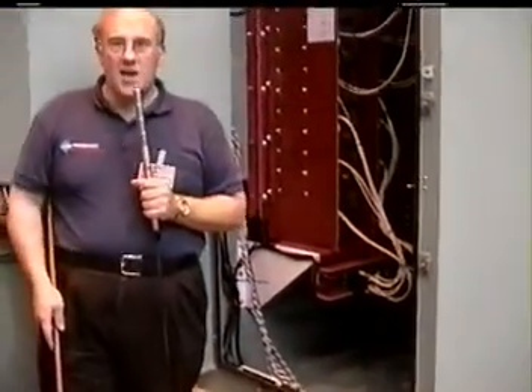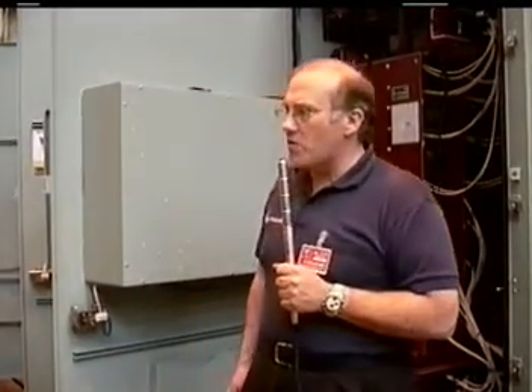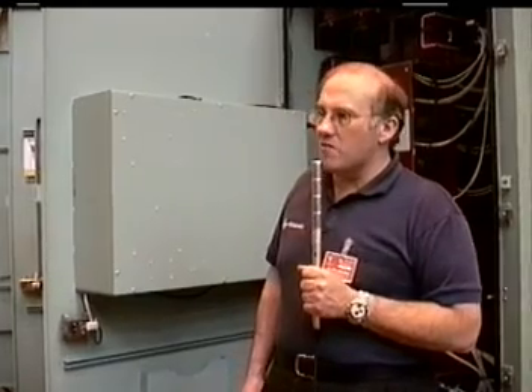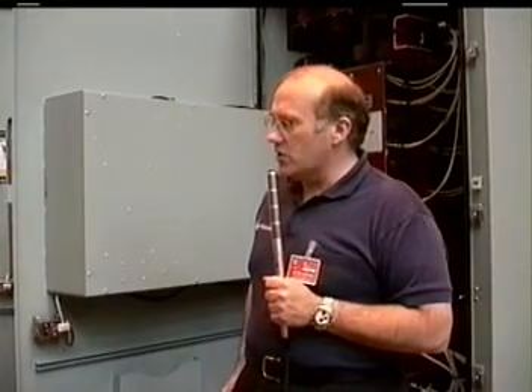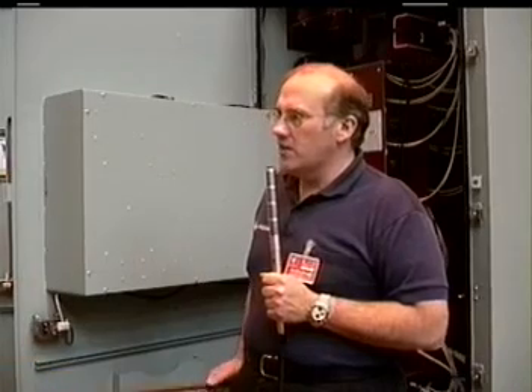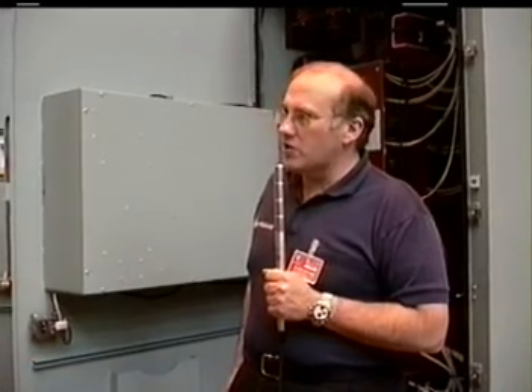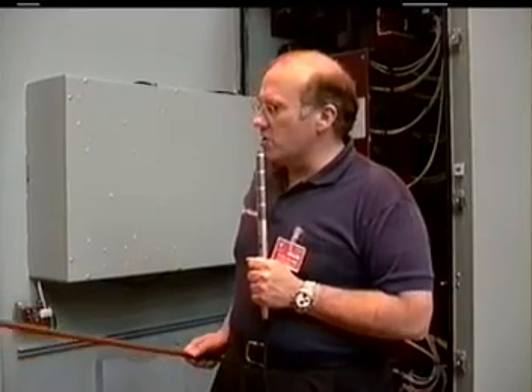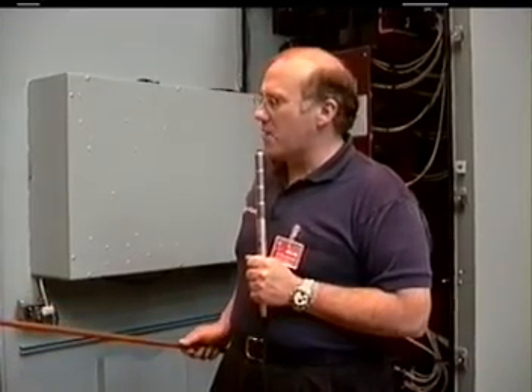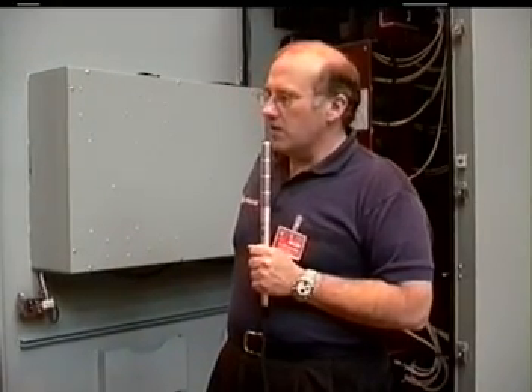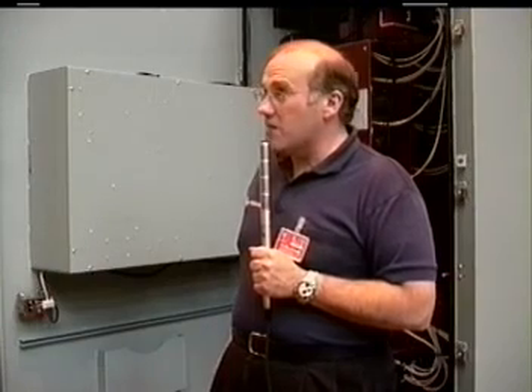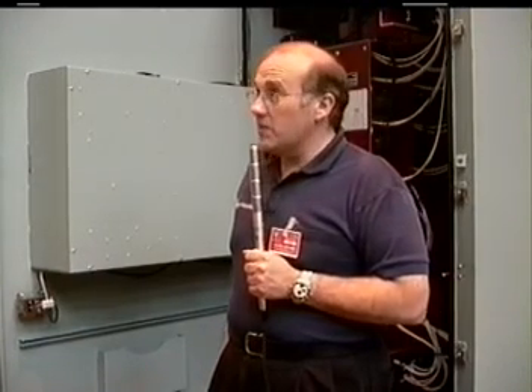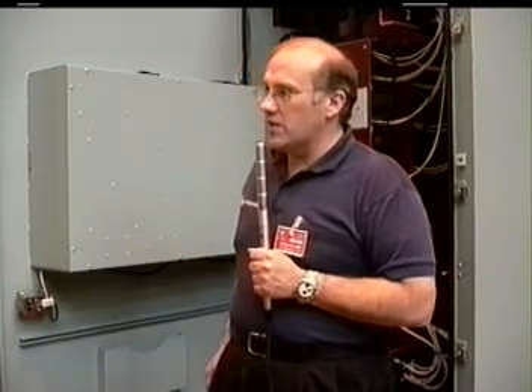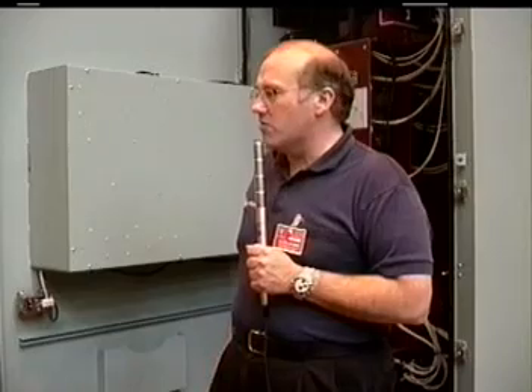This is the whole overview then of the starter. The application for the starter is to operate a 13.8 kV, 5,000 horsepower synchronous motor. The motor is manufactured by GE in Canada, and it is controlled by a separate field exciter package that determines when to actually apply the field to synchronize the motor. The system then is engineered to provide for coordination between the exciter package and the solid-state starter section. Testing of the unit was accomplished in May of 2000 to test the actual motor along with the starter and the exciter package and to simulate field conditions that the customer would encounter during actual operations.